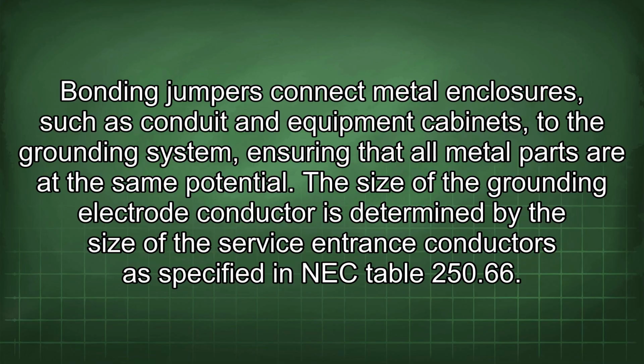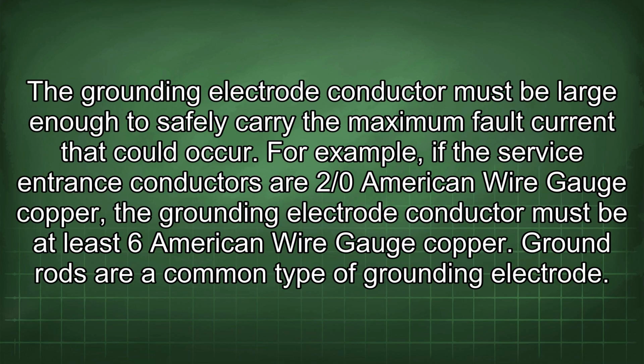The size of the grounding electrode conductor is determined by the size of the service entrance conductors as specified in NEC Table 250.66. The grounding electrode conductor must be large enough to safely carry the maximum fault current that could occur. For example, if the service entrance conductors are 2/0 American wire gauge copper, the grounding electrode conductor must be at least 6 American wire gauge copper.